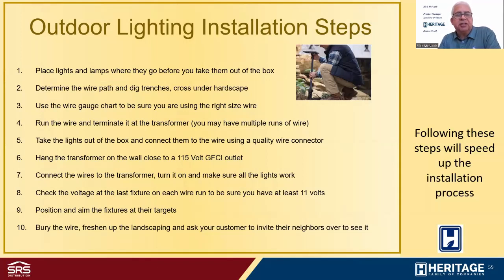Step 8, check the voltage at the fixture, the very last fixture, on each wire run to be sure it has at least 11 volts. So go and find the last fixture on every single circuit you have going out in the yard, take your voltmeter and check that voltage to be sure every fixture on the end of the runs has 11 volts.